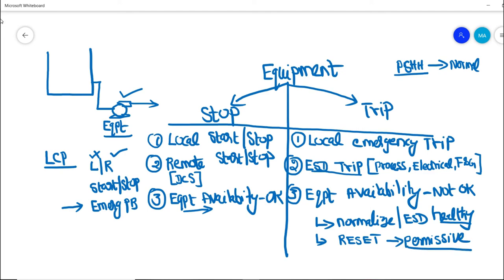Once the reset is done, we have the permissive to start this particular equipment. So now you have seen that equipment stop and equipment trip are not the same — both are different. In a stop condition, a pump or any equipment can be started and stopped any number of times and the equipment availability will always be okay. But in a trip condition — whether a local emergency push button trip or an ESD trip — the equipment availability becomes not okay. We must normalize the ESD, make it healthy, and then perform a reset, after which the trip gets normalized and we can start the pump again.